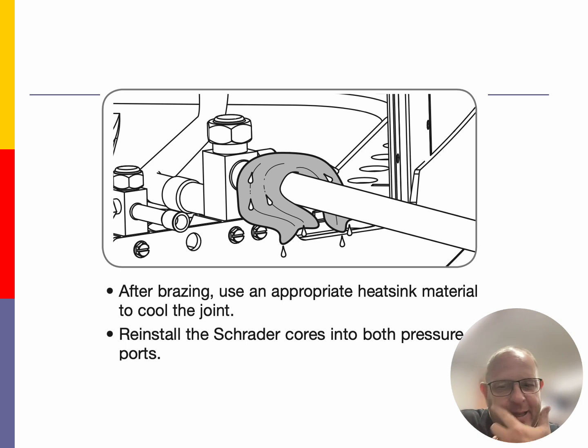depending on how we want to pull vacuums. I know the manufacturers want us to install the cores, but there's a lot of good tools out there now that are allowing us to pull faster vacuums, quicker vacuums, and better vacuums using vacuum rated hoses, valve core removers, and micron gauges that are going to give us decay levels on them after holding that vacuum for a particular amount of time. So reinstalling the Schrader valve cores might be something you do at this point, but it also might be something that we put off until we've actually pulled a proper vacuum on the particular system.